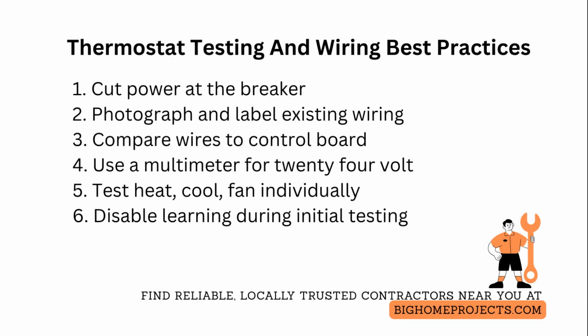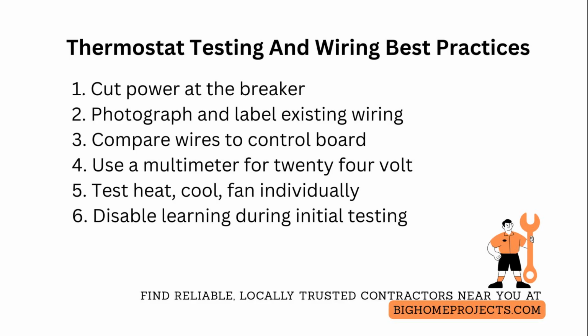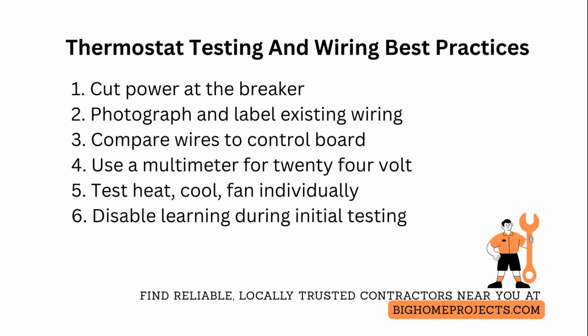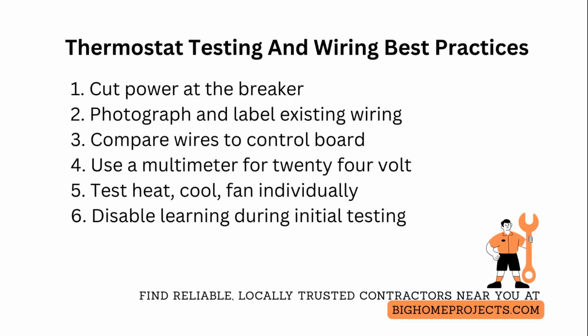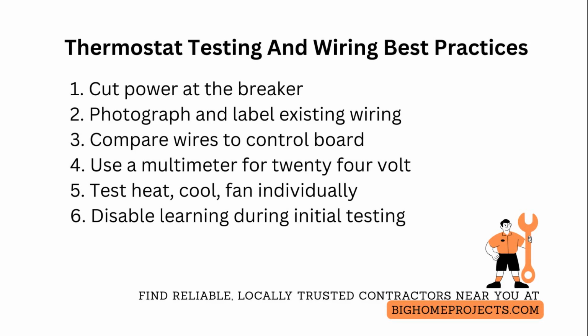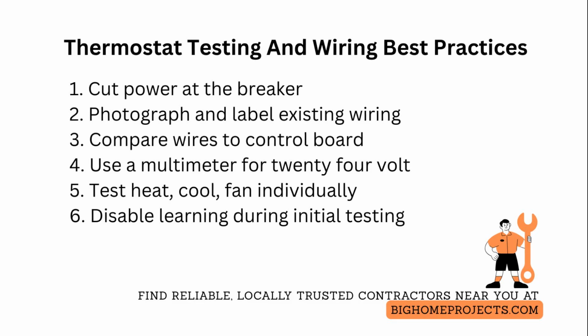Cut power at the breaker, photograph the existing wiring with labels before disconnecting, and compare wire colors to the furnace and air conditioner control board because color standards vary and miswiring is the main cause of failures. Use a multimeter to confirm 24-volt presence and continuity on each control wire, rather than relying on visual inspection.